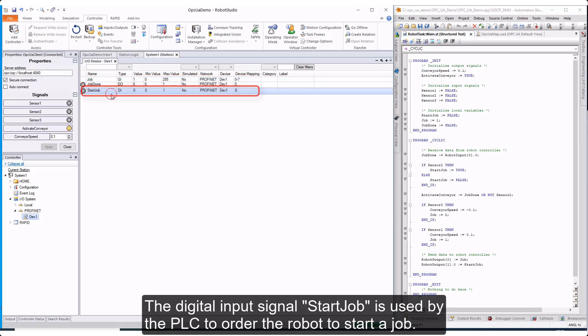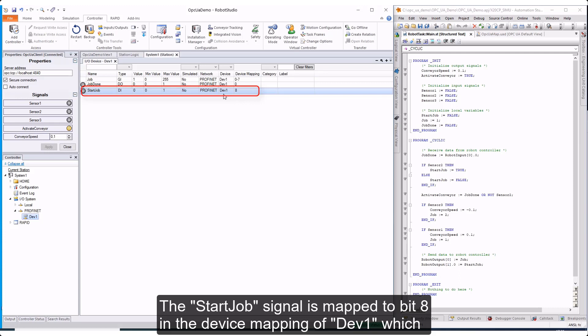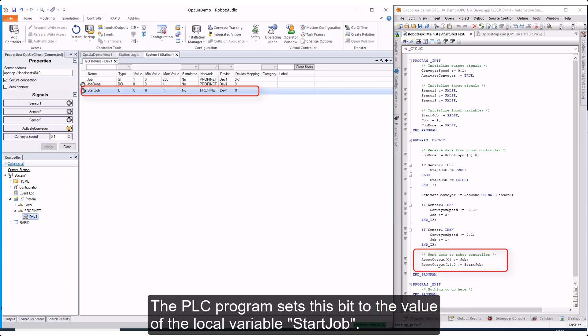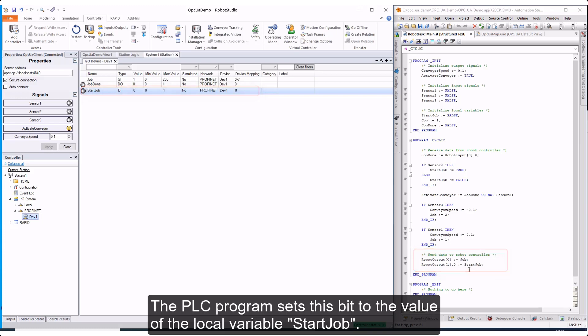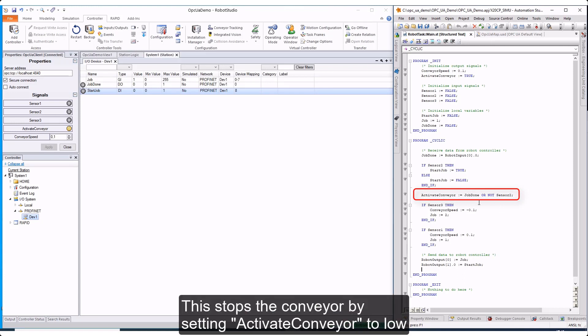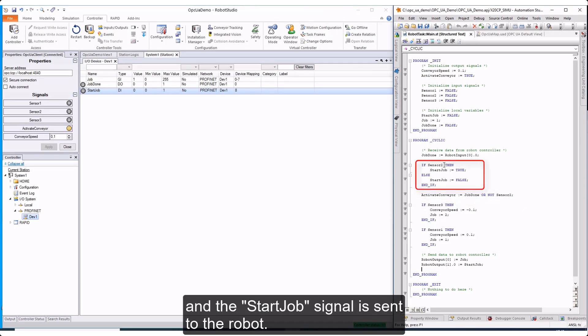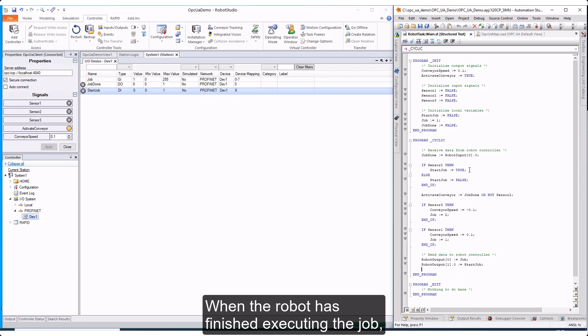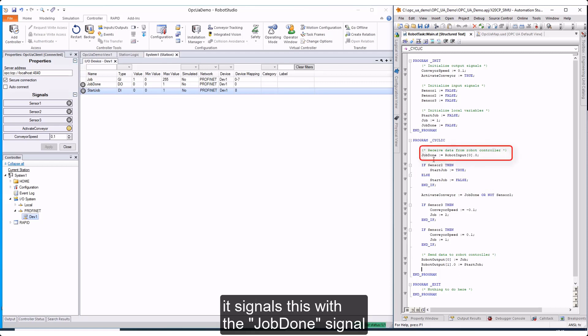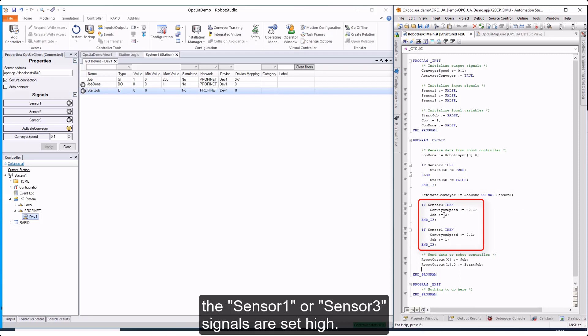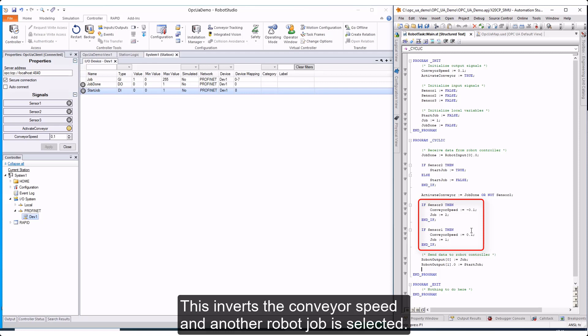The digital input signal Start Job is used by the PLC to order the robot to start a job. The Start Job signal is mapped to bit 8 in the device mapping of DEV1, which corresponds to bit 0 of byte 1 in the variable robot output. The PLC program sets this bit to the value of the local variable start job. When the box reaches Line Sensor 2 in front of the robot, sensor 2 is set high — this stops the conveyor by setting Activate Conveyor to low and the Start Job signal is sent to the robot. When the robot finishes, it signals this with Job Done, which starts the conveyor again. When the box reaches Line Sensor 1 or Line Sensor 3, the sensor 1 or sensor 3 signals are set high, which inverts the conveyor speed and another robot job is selected.